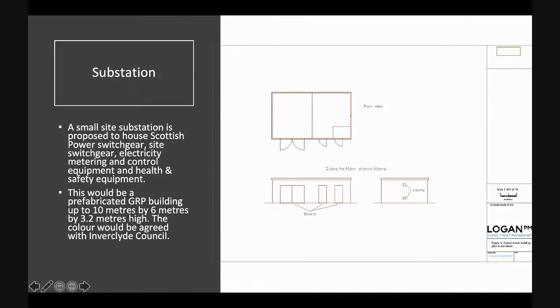The substation building itself is a small glass reinforced plastic building, containing all the equipment we need to get the electricity to and from the grid and back again. That's 10 metres by 6 metres by 3.2 metres high, with a colour that we agree with the council - that should say Angus Council, not Inverclyde, apologies for that.